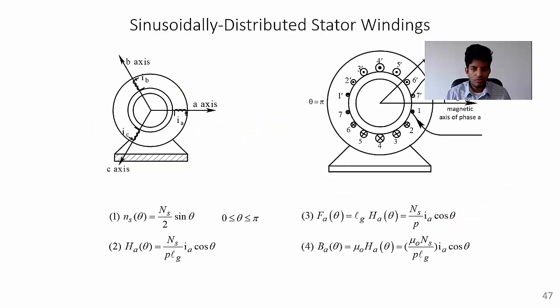In the next 1 hour of the session, we will look at extending the concepts of DC motor speed control and applying them to induction motor and permanent magnet synchronous motor speed control. One of the major shortcomings of a DC motor drive is the requirement for commutator brushes. These carbon brushes lead to sparking and wear down as they slide against the copper slip rings. In addition, they also cause notches in the torque response.